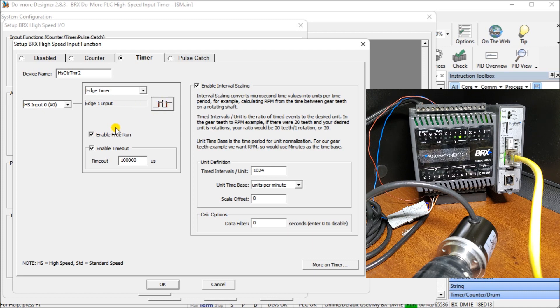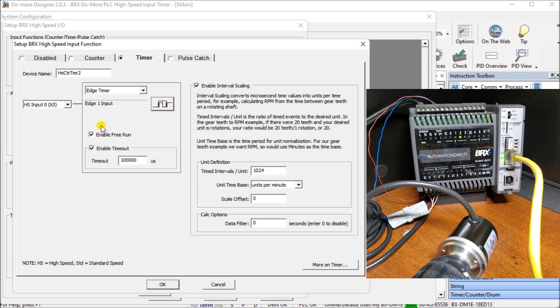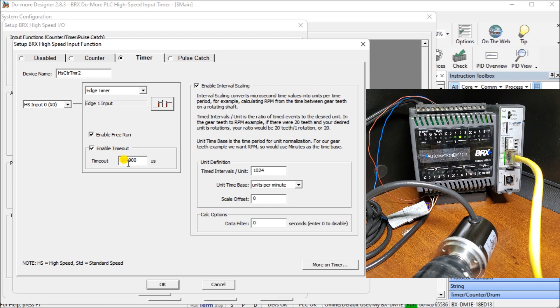We're also going to enable free run. What that will do is automatically reset our time each time that we run, so I don't have to manually do it. It should give us a value right away. Then we're going to enable the timeout. The timeout I have labeled is 100,000 microseconds, or 100 milliseconds. So every 100 milliseconds, if it does not see a pulse, it will reset that timer.